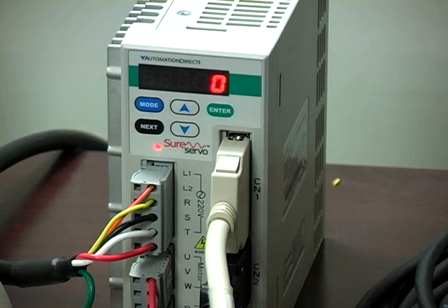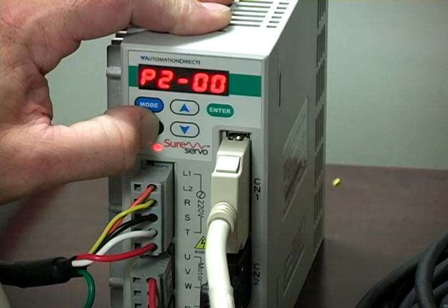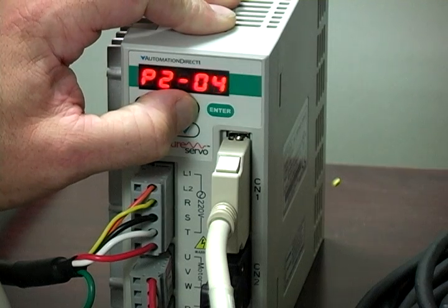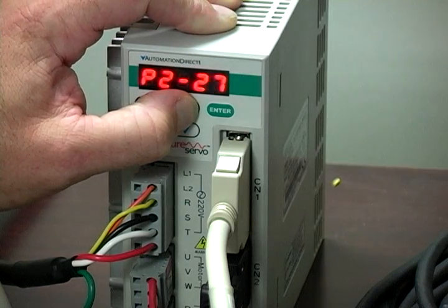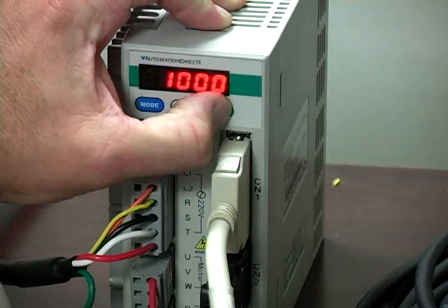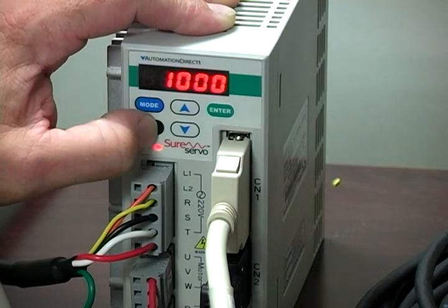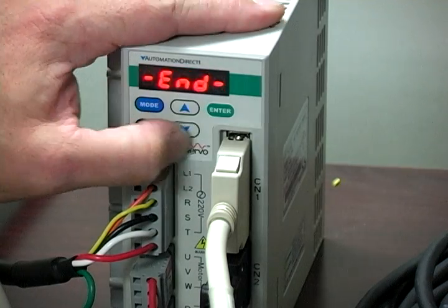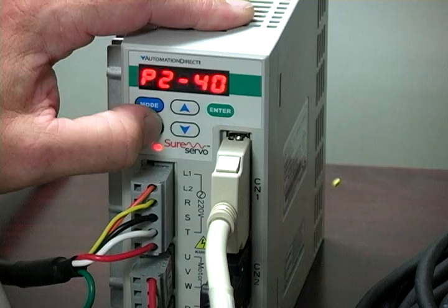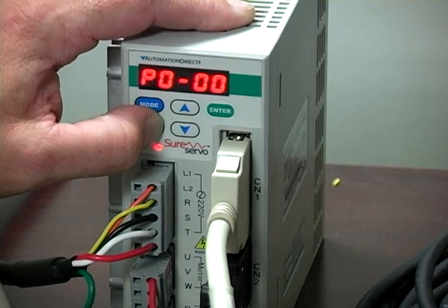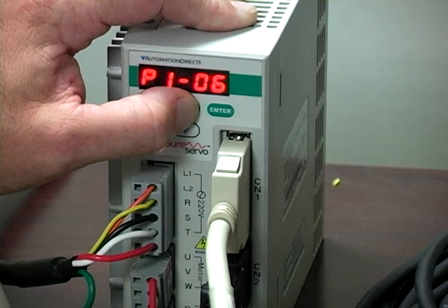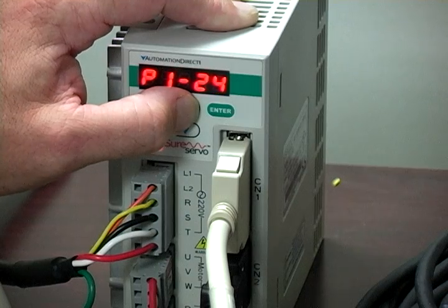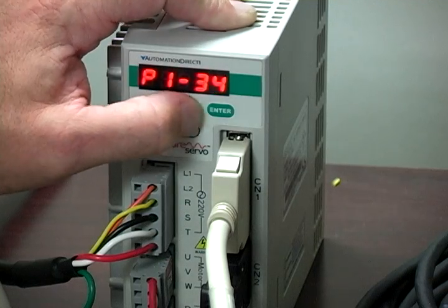Let's increase the speed of a move and slow the acceleration. I'll increase the speed of position move number 5 by changing P2-40 to 3000 RPM. The default was 1000. I'll slow the acceleration time P134 from its default value of 200 milliseconds to 2000 milliseconds.